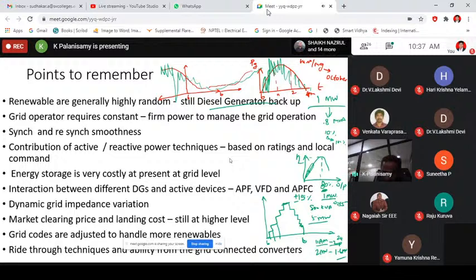For example, if the frequency is increasing from 50 Hz to maybe 50.05 or 50.1 and so on, what I can do is start to decrease the active power injection to the grid. By applying MPPT or some other technique, I can try to reduce the active power injection. Similarly, if the frequency is falling from 50, it can come to 49.95 or 49.9, something like that. What I will do, by having a short time backup, is try to increase my active power injection. This is called inertia.